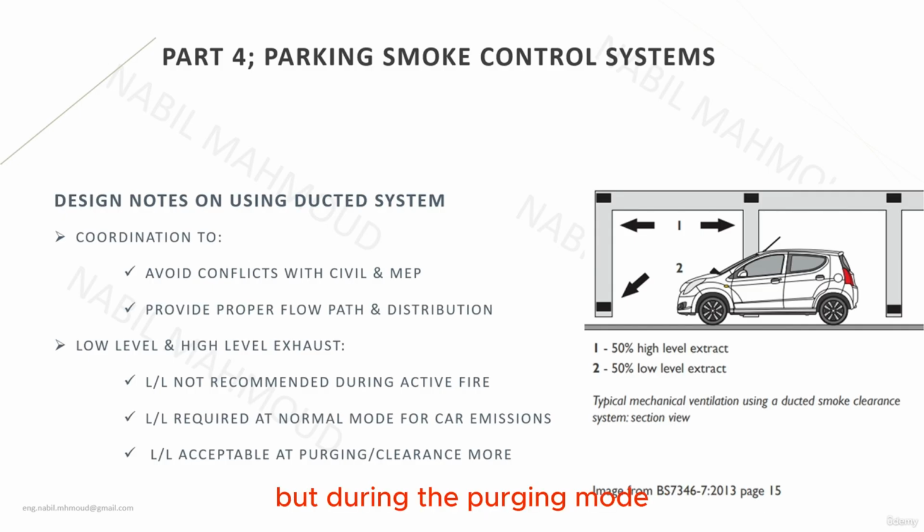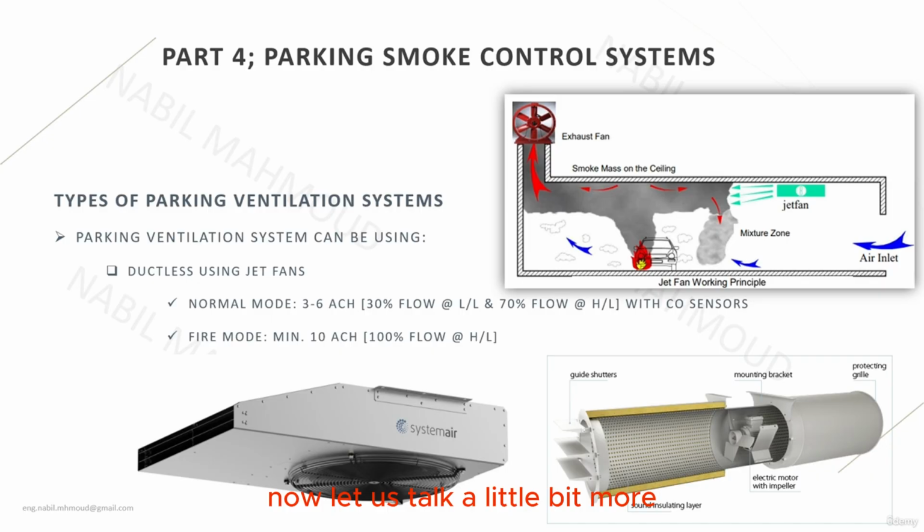But during the purging mode, since the place is already unoccupied and already filled with smoke, there will be no objection to using the suction from the low level and the high level. However, during the evacuation, it is very risky and very dangerous to use the exhaust point from low level.